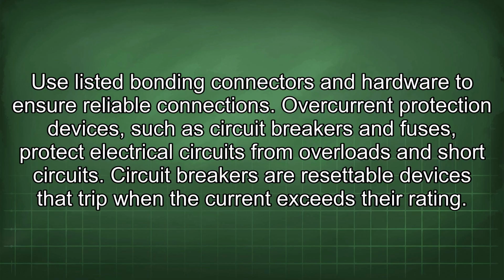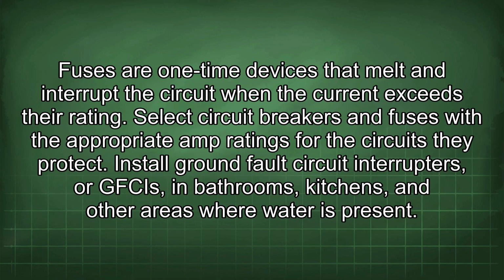Overcurrent protection devices, such as circuit breakers and fuses, protect electrical circuits from overloads and short circuits. Circuit breakers are resettable devices that trip when the current exceeds their rating. Fuses are one-time devices that melt and interrupt the circuit when the current exceeds their rating. Select circuit breakers and fuses with the appropriate amp ratings for the circuits they protect.